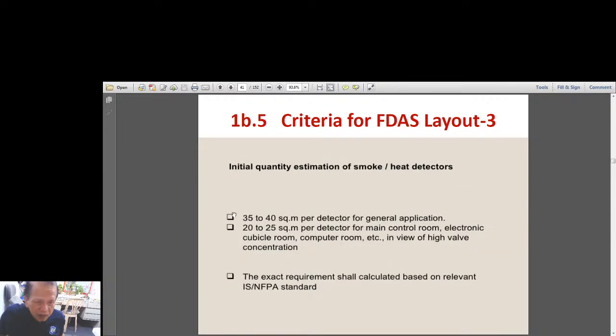Okay, and here is an important thing. The number of smoke or heat detectors could be governed by this. For detectors in general application, up to a maximum of 40 square meters of room, one detector, meaning one. You can put two, but at least there should be one. But for special rooms, like rooms with equipment such as control rooms, electronic cubicle room, computer room, battery room, electrical room, switchgear room, and so on and so forth, detectors should be provided in every 25 square meters of area. So that means that if it is a 50 square meter area, you should have a minimum of 2 detectors. If you have 100 square meters of area of this control room or cubicle room or computer room, then you must have at least 4 detectors.